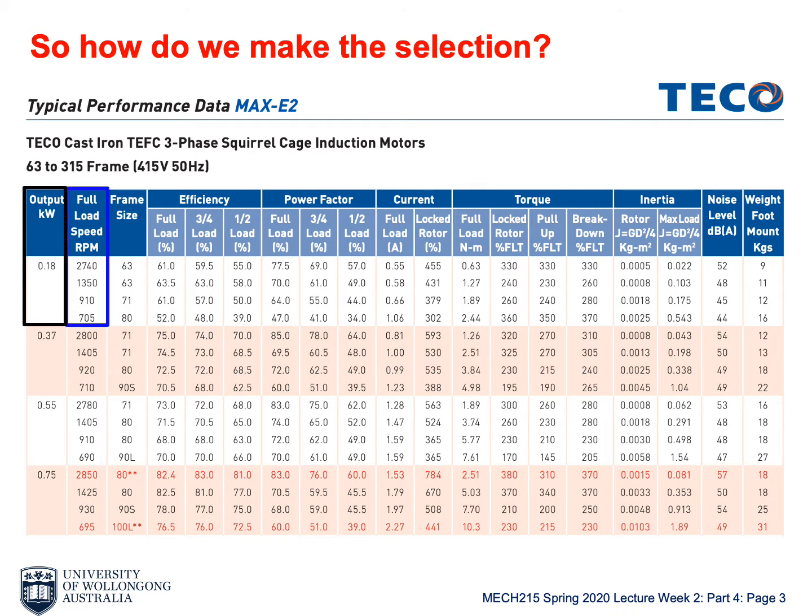The second column is the RPM. For each particular output power, you get 4 different RPMs, and this corresponds to the different number of poles the motor has. So for a 2-pole motor, it will have 3000 RPM as its nominal speed, and 2740 is actually the full load speed for that particular motor, with 4% of slip.